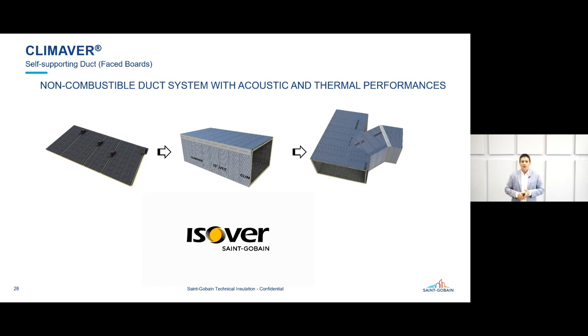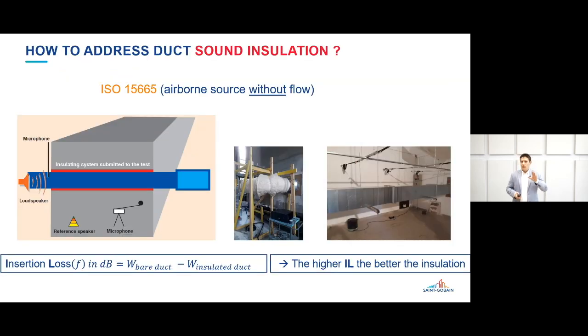Coming back to the acoustics, we'll start with sound insulation, following the international standard 15665. The way to test is you have a loudspeaker outside the room and a duct crossing the room, with a microphone measuring the vibration of the duct, so you can compare the results with different systems installed in the room.